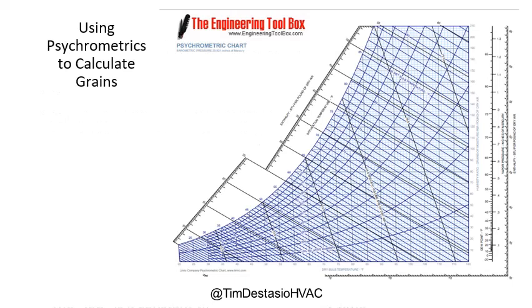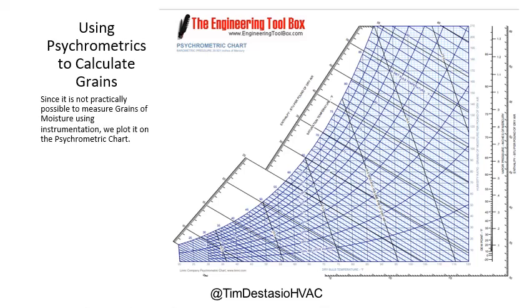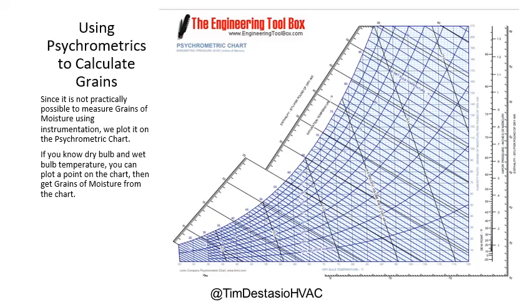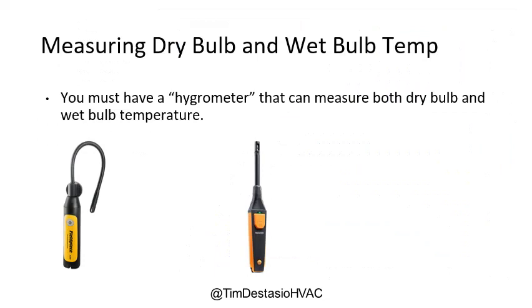To calculate the grains of moisture difference, we go to the psychrometric chart or use a psychrometric app. The psychrometric chart is useful because we can plot points that represent the properties of air. It's not practically possible to measure grains of moisture using instrumentation directly, so we plot it on the psychrometric chart. If we know our dry bulb and wet bulb temperature, we can plot a point and get our grains of moisture. An instrument that can measure both dry bulb and wet bulb temperature is called a hygrometer.